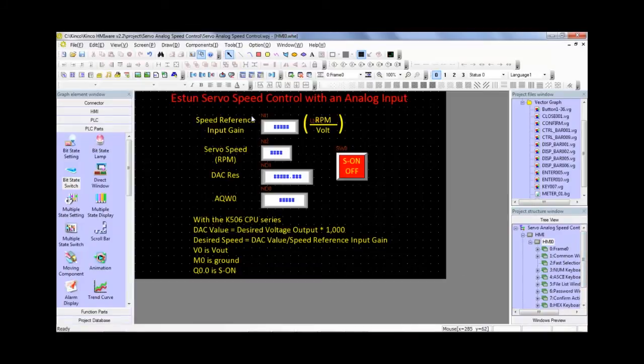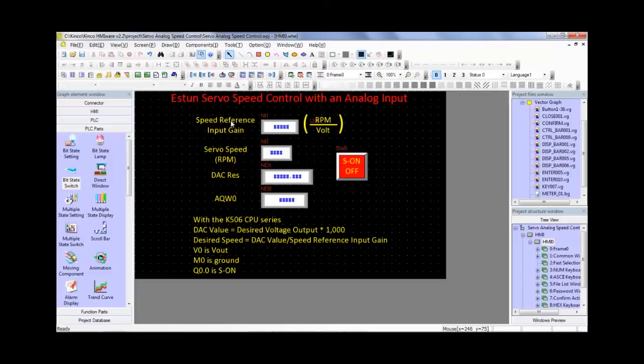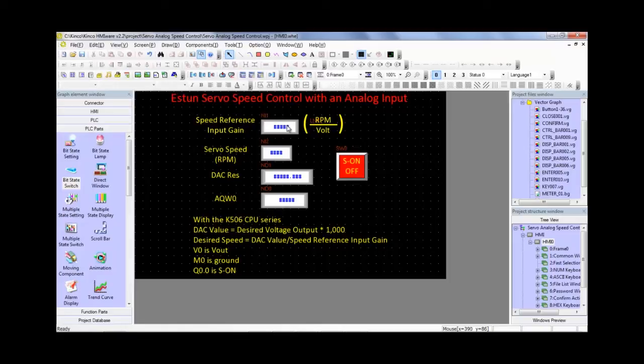Right here we have a numeric input, which is already set in the servo. That numeric input is the speed reference input gain. So, this is just used to get a multiplication factor, but again, it's already set in the servo unit, but we do have to set it in the HMI so that we are getting the correct RPM output.